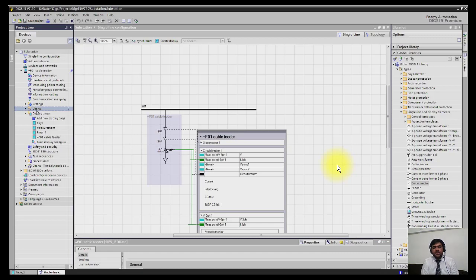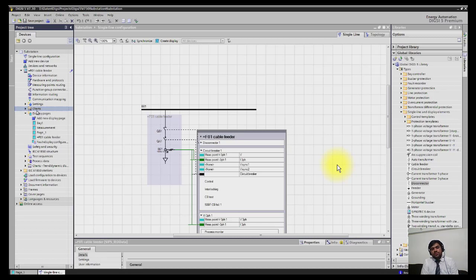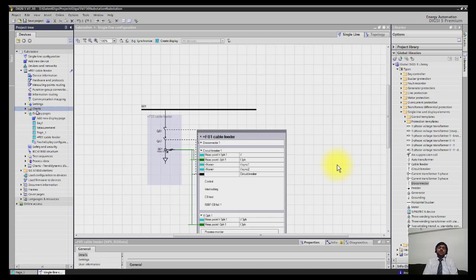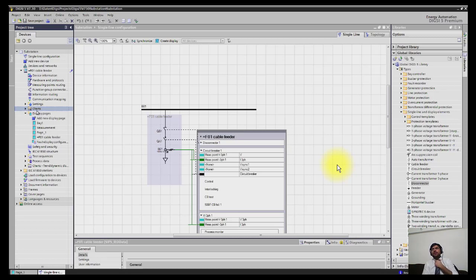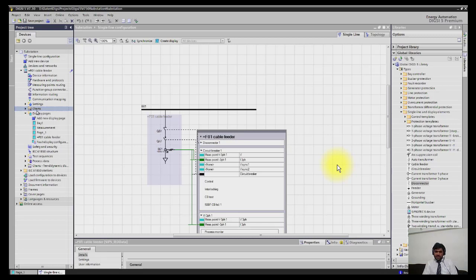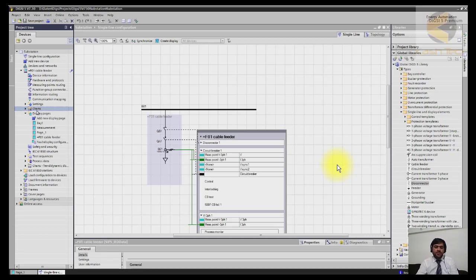The breaker can be operated open or close irrespective of isolator status, but if the isolator status is intermediate, the breaker should not operate. Similarly, the isolator should only be able to operate if the breaker is open. If the breaker is closed or its status is not clear or intermediate, the isolator should not operate. We will see how we can draw these interlocks using DIGSI.